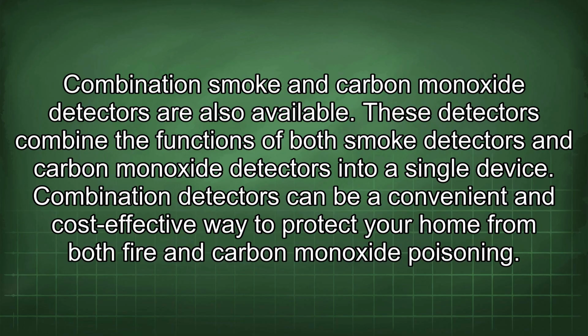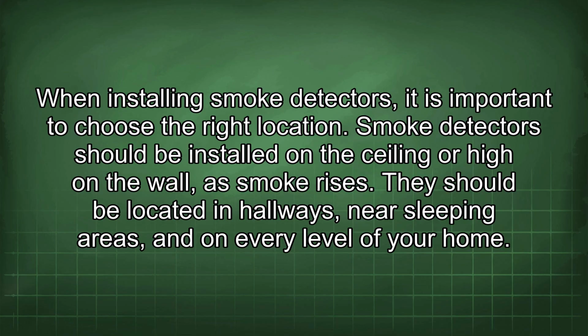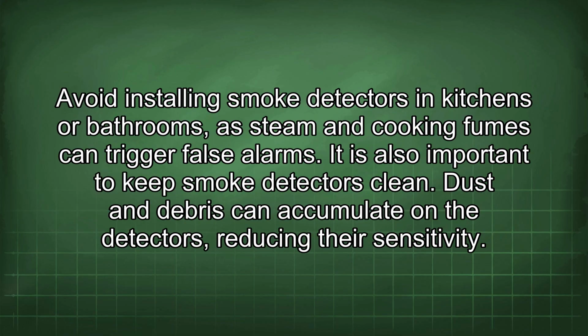Combination smoke and carbon monoxide detectors are also available. These detectors combine the functions of both smoke detectors and carbon monoxide detectors into a single device. Combination detectors can be a convenient and cost-effective way to protect your home from both fire and carbon monoxide poisoning. When installing smoke detectors, it is important to choose the right location. Smoke detectors should be installed on the ceiling or high on the wall as smoke rises. They should be located in hallways, near sleeping areas, and on every level of your home. Avoid installing smoke detectors in kitchens or bathrooms, as steam and cooking fumes can trigger false alarms.